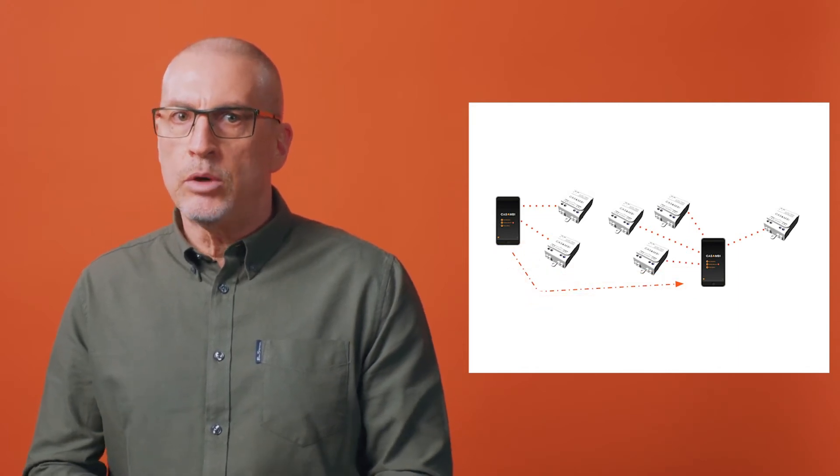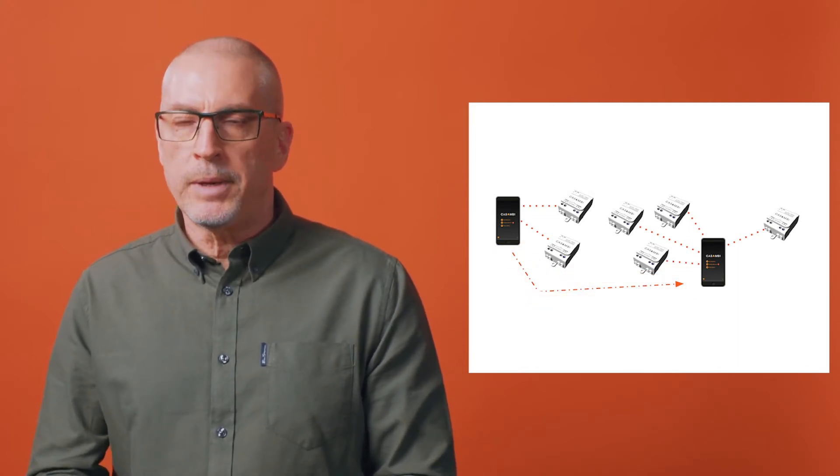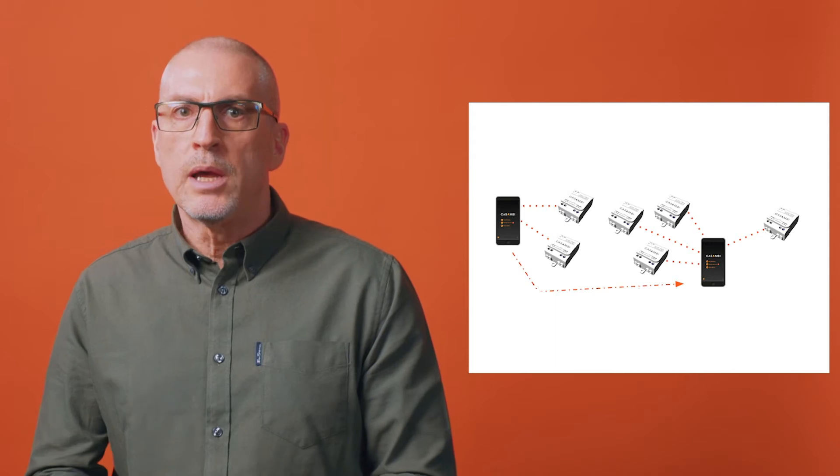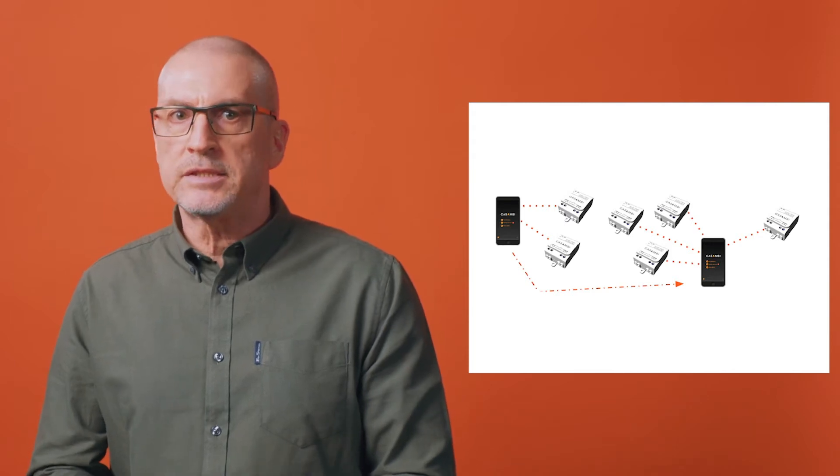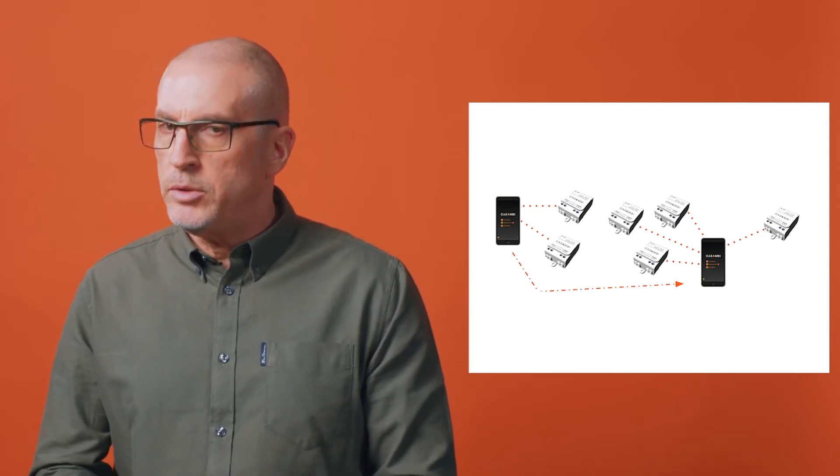In this way all devices will be paired to a network but that doesn't necessarily mean they'll communicate together. After pairing, devices directly communicate with each other via the mesh. However, if a device has been positioned out of communication range of others or if materials are blocking direct communication between Casambi enabled devices, you may experience what we refer to as an island issue.